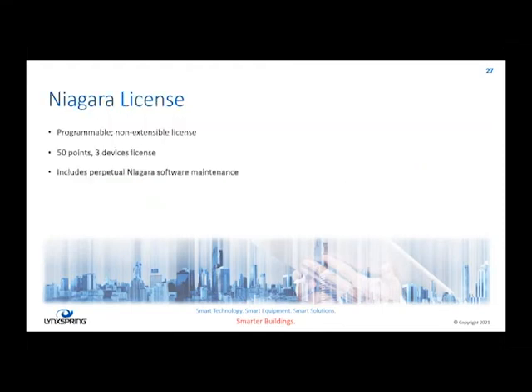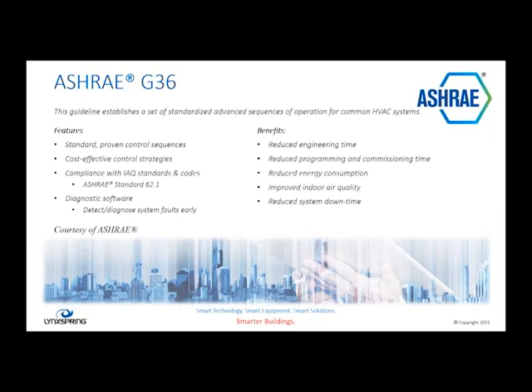Our Niagara license. We have a special license for these controllers. So number one is when you buy a 414, you cannot upgrade that license. It comes with the license that it has. It's 50 points, 3 devices. So it's limited on the number of BACnet connections that we can make to 3 different devices. We typically only use 1, and the 50 points that we bring in. But the great thing about this license is that it doesn't require any maintenance. And when version 4.11, 4.12 comes out, all you have to do is tell it to fetch the new license. So that was a really good thing that Tridium gave for us.